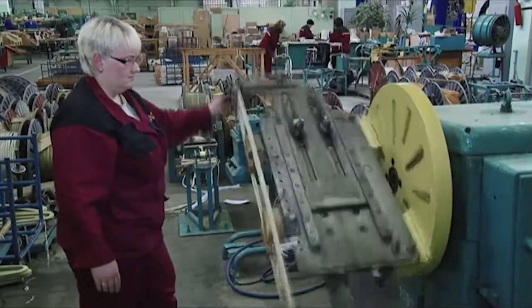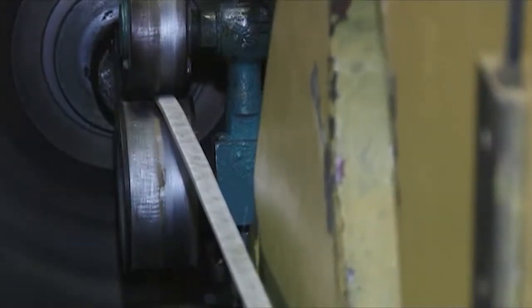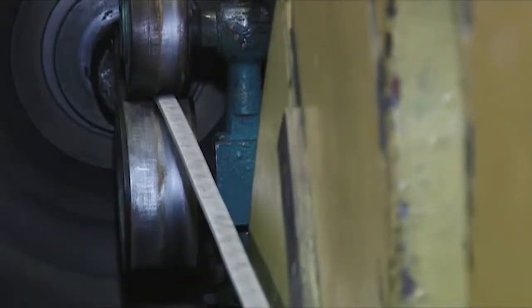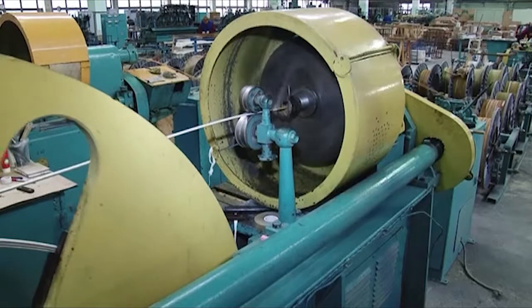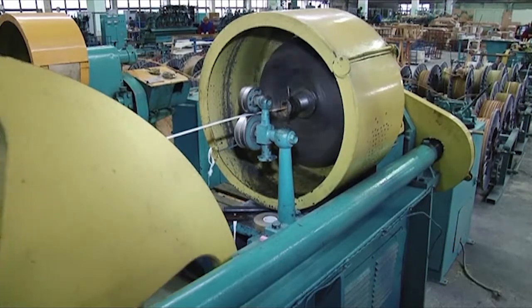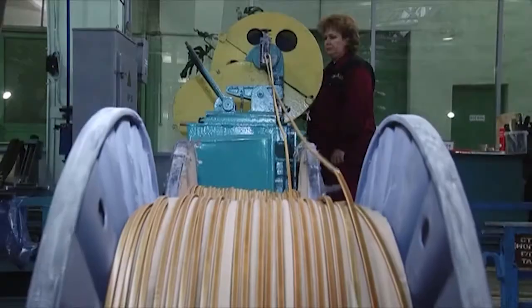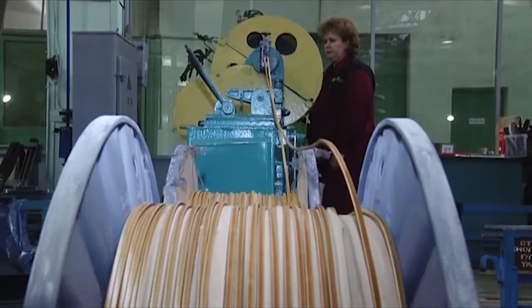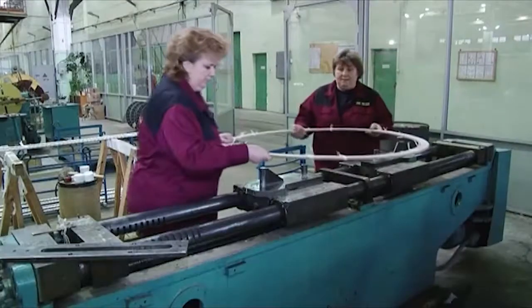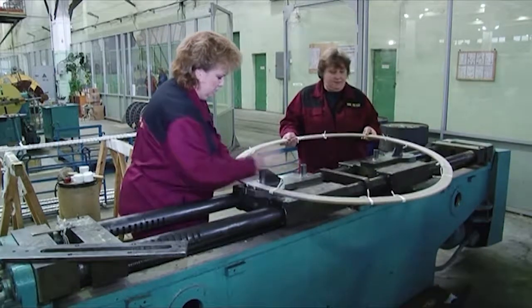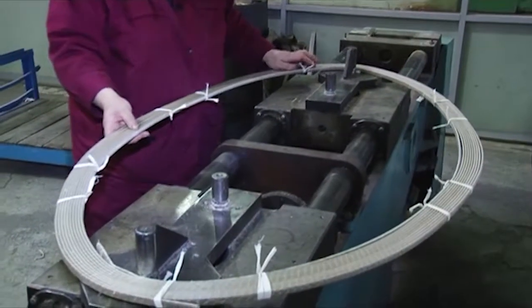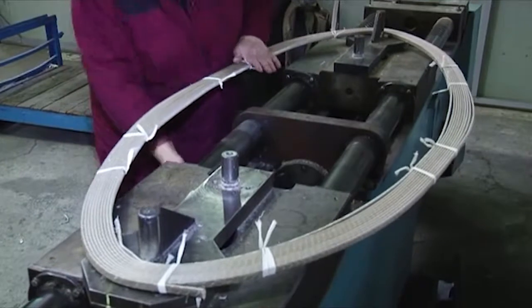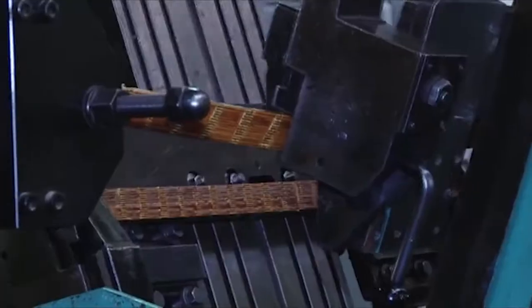The manufacture of the coil includes several stages. Firstly, insulated wire is boat-shaped wound for electric motors below 6 kilovolts. Then the wire is additionally insulated if turn-to-turn insulation is required for high-voltage machines of up to 11 kilovolts or 13.8 kilovolts in 60 Hz. After that, the winding is made in the form of a circle with subsequent boat-shaped stretching.